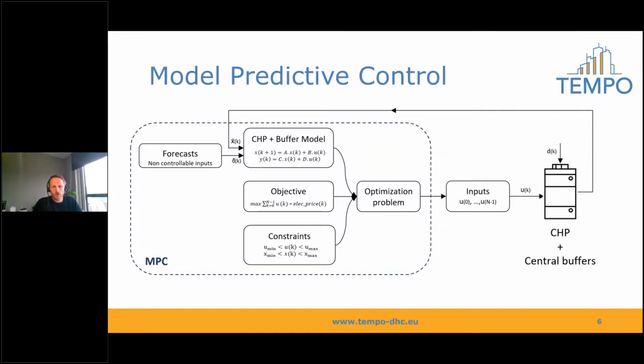Plus, once we switch on the CHP, it has to run for at least 2 hours. So you cannot just switch it on and off every quarter. For the central buffers, we put two constraints. The state of charge, which we decide upon based on the temperature measurements of the buffer, has to stay between 30% and 80%, because then we still have some safety left if it goes below 30%. And the buffers have to be at a temperature between 55 and 80 degrees. Once we put all this together, we get the optimization problem. We calculate the outcome, and this will be a plan for the CHP for the next 24 hours.